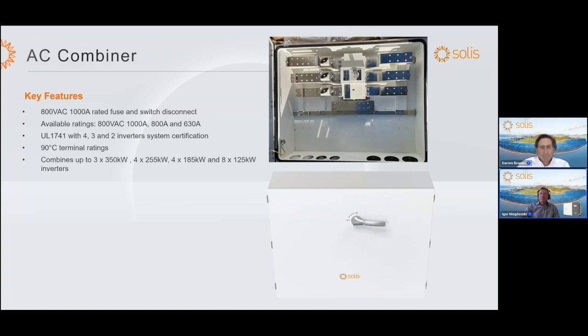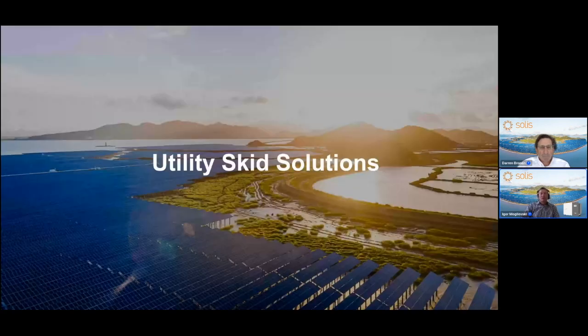It can combine 3 350 kilowatt inverters, 4 255, 4 185, and 8 125 inverters. So you could have multiple inverter combinations here with this enclosure, with this AC combiner. You can use up to 250 to 750 kcmil incoming cables, and outgoing cables could be 600 to 1000 kcmil. So it gives you a lot of flexibility on the cable sizes. It is UL NEMA 3R rated. And now we'll present the utility skid solution.